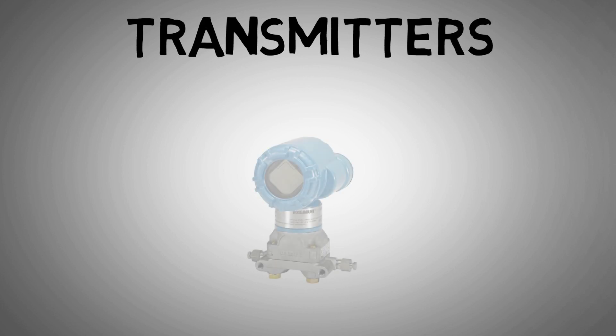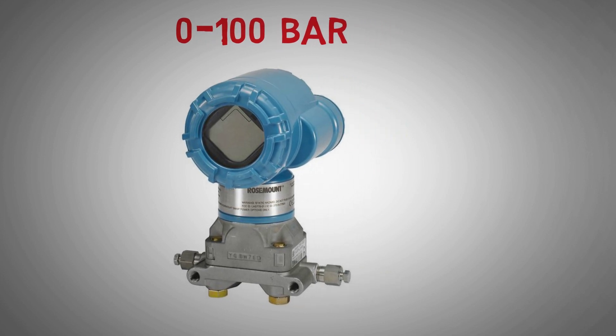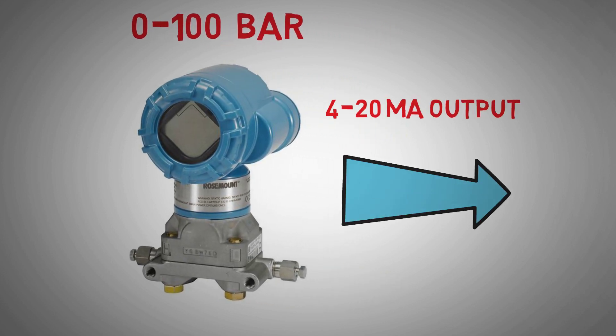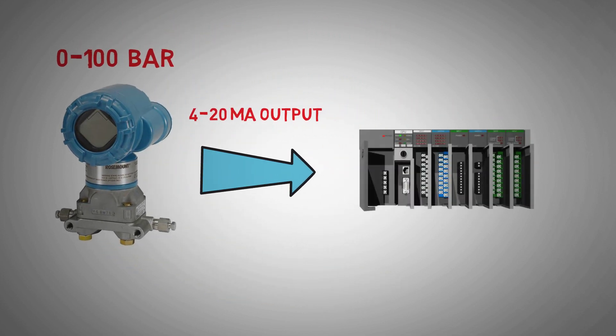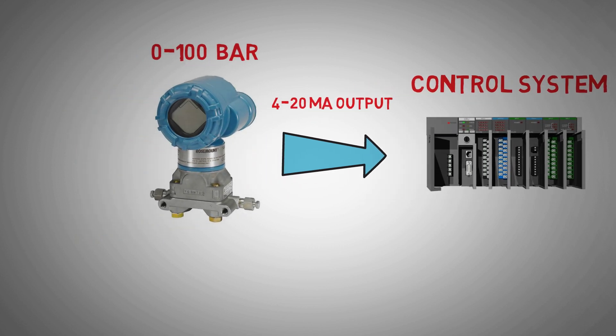A transmitter gives an analogue variable output in response to varying process conditions. A pressure transmitter may be ranged 0 to 100 bar, where it gives a 4 to 20 mA current output to our control system in response to the pressure input.